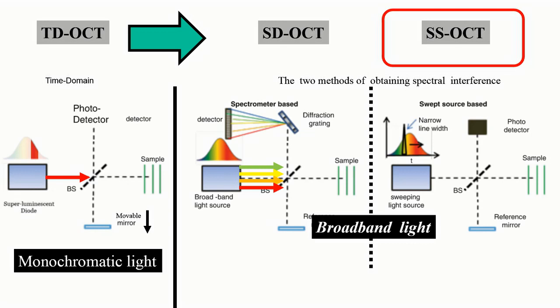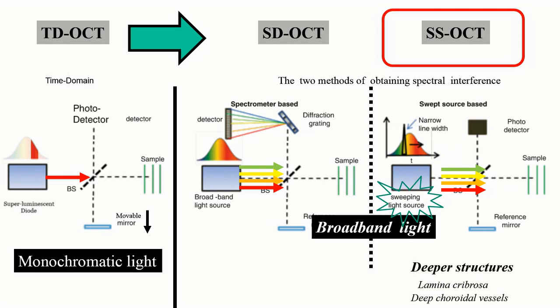Swept source OCT also uses broadband light, but the separation of wavelengths occurs at the level of the source rather than the detector. A narrow linewidth laser is gradually swept through the spectrum to send different wavelengths sequentially. In spectral domain OCT the separation occurs at the detector, whereas in swept source OCT it occurs at the source. Swept source OCT has the advantage of imaging deeper structures, such as the lamina cribrosa and deep choroidal vessels. Spectral domain can image these structures to a limited extent using a technique called enhanced depth imaging by positioning the instrument closer to the eye, but the quality is inferior to swept source OCT.